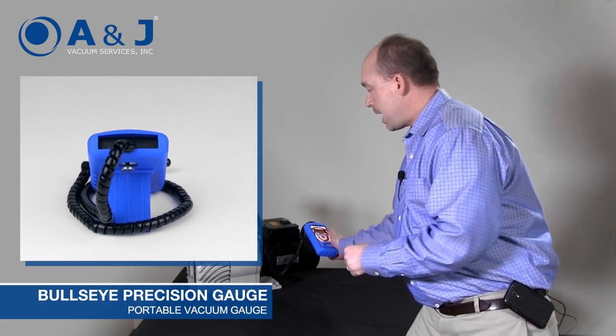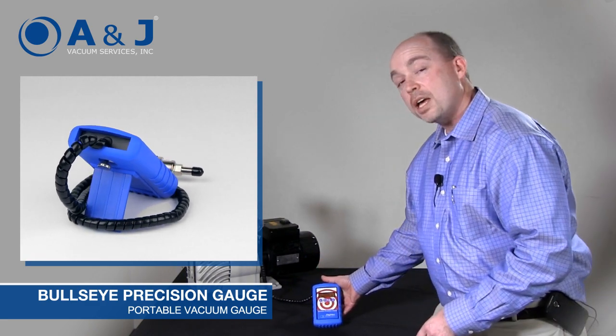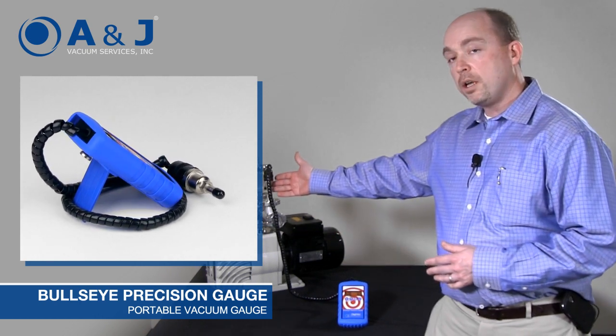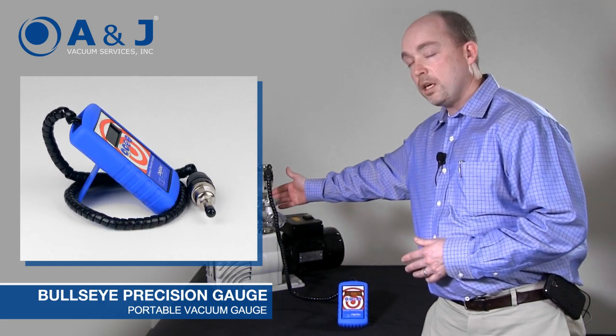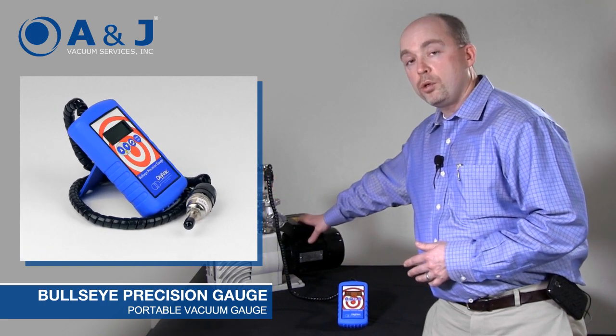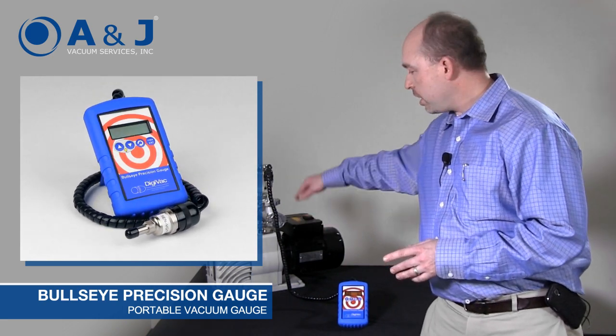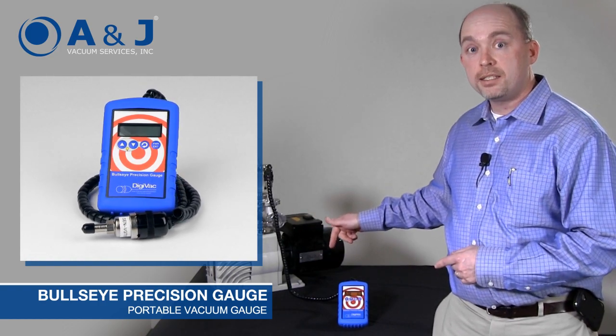Now we'll talk about the setup so we can actually show you the Bullseye at work. We have the Bullseye Precision Gauge connected to a Varian 531 equivalent sensor, plumbed in via a small vacuum manifold with a bleed valve into a two-stage pump. For expediency, I've already evacuated down to about 10 millitorr and now we're bleeding back up.